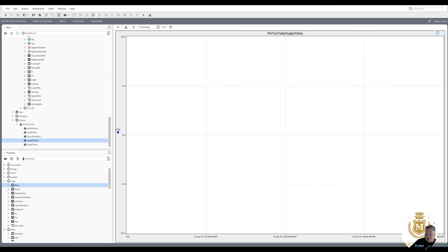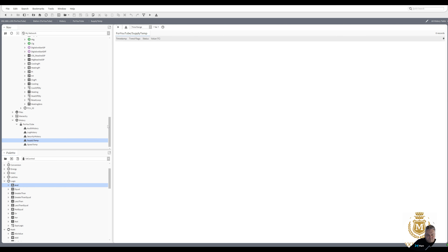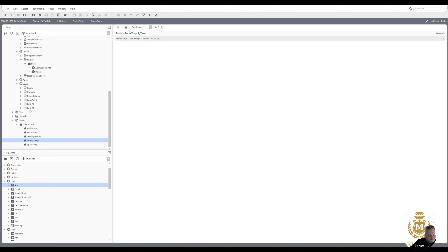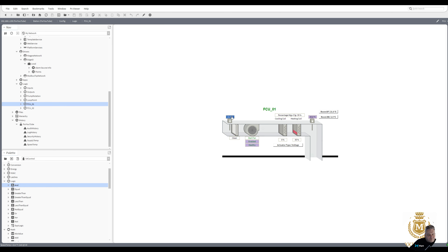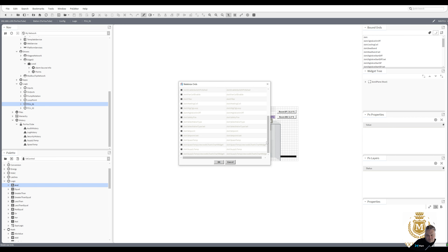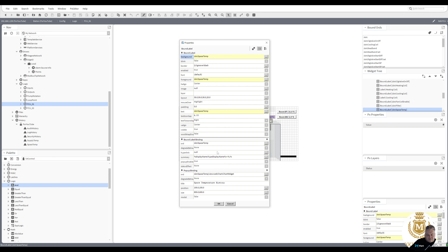I don't want history chart, I want history table. There's nothing there at the moment - it will record in 30 minutes time, about 25 minutes time looking at the clock. So we'll leave that as it is. That graphic will work now because it's looking at that point. What we do want to do is relativize the ORDs - I think that's already been done, yes it is. So we're physically looking at the space temperature in that folder now and that's the history for it.